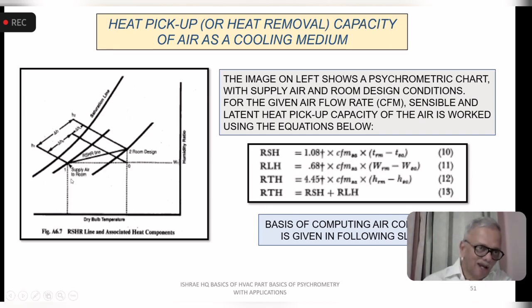What I am saying here is I am supplying air at this moisture content and dry bulb temperature. So that is the leaving coil condition, the supply condition. And I am supplying X air quantity or X CFM. So I want to calculate how much capacity this air, X quantity at that condition, has to reach the room design of whatever your 75 or 74. How much heat? Because you have calculated the room sensible heat and the room latent heat, and now you have decided the condition of the supply air and the air flow rate.